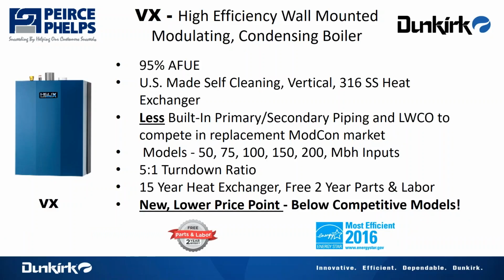So then we move on from the VLT to the VX. It's the VLT's little brother. 95% AFUE, still has the same US-made ECR design vertical laser tube 316 heat exchanger. So enjoys the same heat exchanger, all the benefits and value of that. However, it is built less the primary secondary boiler piping and without the low water cutoff. Why would we do that? Why would we have another boiler?